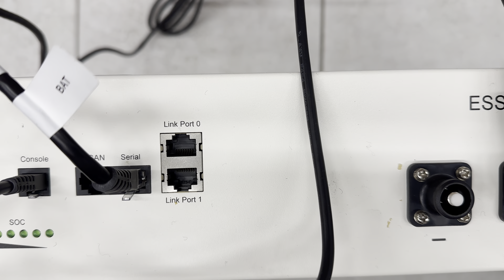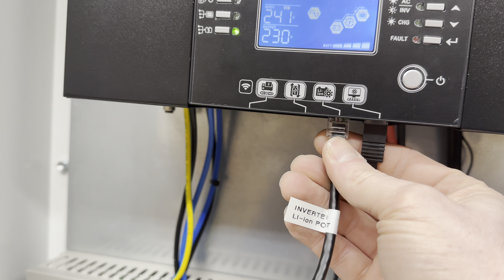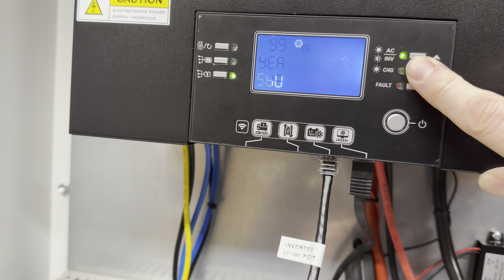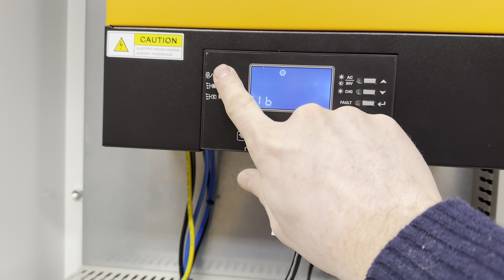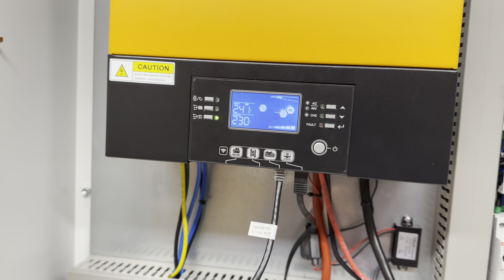This is the serial port or the RS485. We connect this special cable back to the lithium-ion port of the inverter. And in menu 5 we select the protocol LIB. Here we are. That's our LIB protocol. When the battery icon is flashing, it means that we established the BMS between the batteries and the inverter. So very careful to use the BMS cable to the right port.